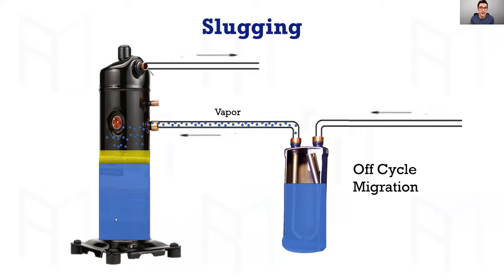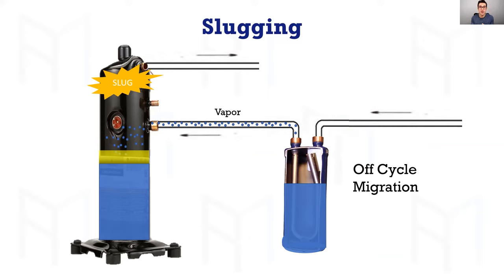If that compressor is cold or the crankcase heater is not working, it's very important to understand that when refrigerant travels back into the compressor, it'll condense in that oil. When that compressor starts up, you get a slug, which can break the flanks. The scroll set has flanks — the walls are called flanks — and when the compressor tries to compress oil or liquid refrigerant, it breaks those flanks.